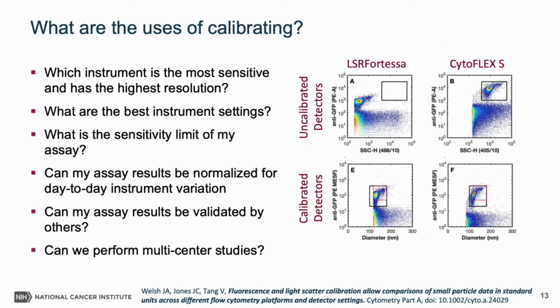So there are many reasons why you'd want to perform calibration on a flow cytometer. It will allow you to decide which instrument has the highest sensitivity and resolution, and quantify which settings are best for any particular instrument. It'll also allow you to define the limit of sensitivity for your assay and normalize for day-to-day variation.